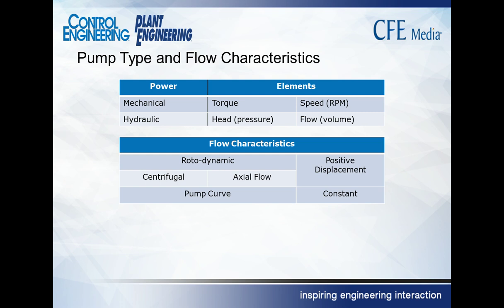Okay, so just to get things in scope, a pump is a device that changes mechanical energy, mechanical power, into hydraulic power. The mechanical power is torque on a rotating shaft and speed of the rotating shaft. And when it's changed into hydraulic power, that becomes the head, which is analogous to pressure, and the flow, which is the volume or quantity of the liquid that's pumped.